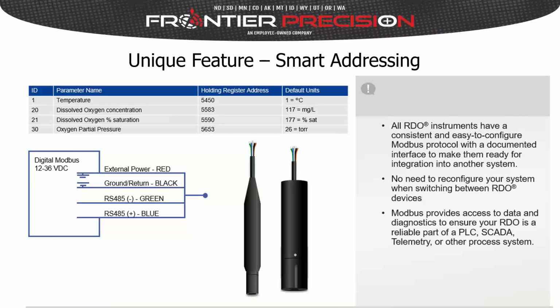Another unique feature for those that are using the sensor with data loggers or SCADA systems is that the RDO Blue is a Modbus sensor with smart addressing. So it makes it really easy for you to swap sensors out at your sites to possibly take one into the lab or do other things with it without configuring your SCADA system. So we essentially have a 4-wire system, 12 to 36 volt DC digital Modbus RS485, and the register addresses are always the same. So it should be very easy for data logging or SCADA system setup.